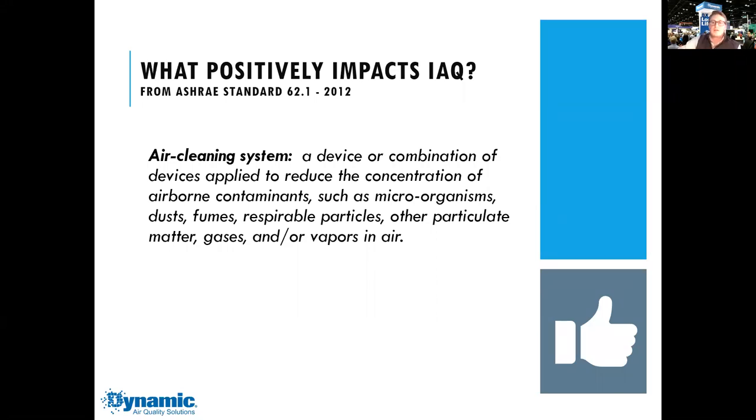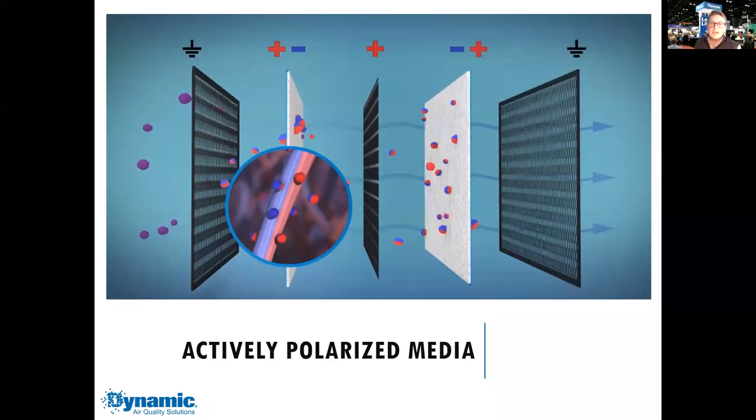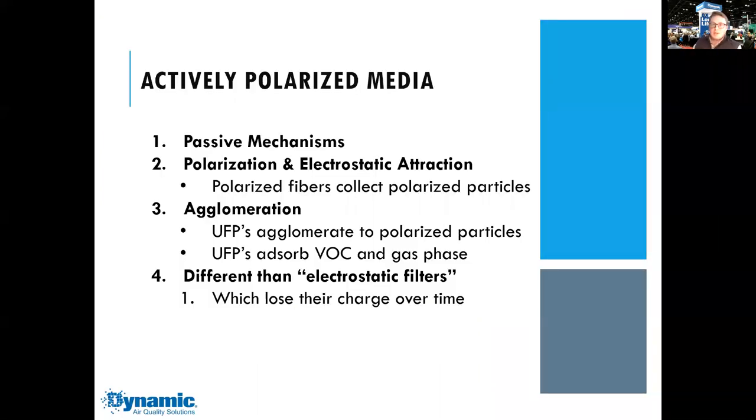So Dynamic is considered an air cleaning system because of our actively polarized media. And the reason being is because we use passive mechanisms like any regular filter. So the filter products that do have a MERV rating associated with them, those products are tested as passive unpowered filter media. But when they are powered, you get a couple extra benefits, and those are polarization, electrostatic attraction, and agglomeration. So polarized fibers are going to collect polarized particles, and that creates bonding sites, and that helps take out small particles.